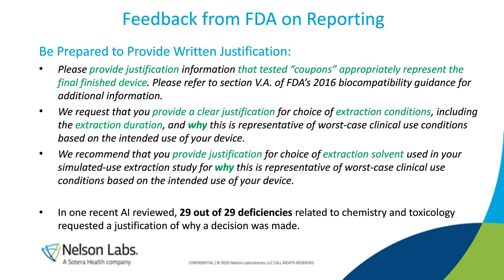So this also, to me, represents a shift where maybe they've been asking for a lot more detail with chemistry, and they've made a bunch of policy decisions on, for example, requiring exhaustive extractions and the three solvents, a polar, a midpolar, and a nonpolar, and so on. But when they just apply those recommendations in a blanketed fashion, then they hear back from people like me, Dr. Jorgensen, where I'm like, wait a second, exhaustive extraction doesn't make sense because this is an all-metal device and for X, Y, and Z reasons.